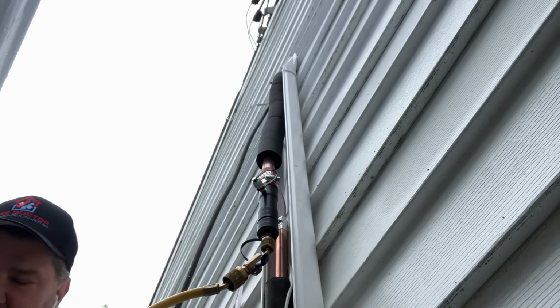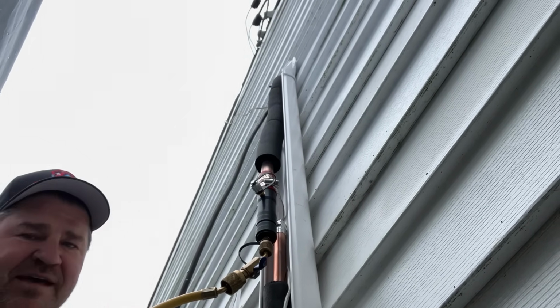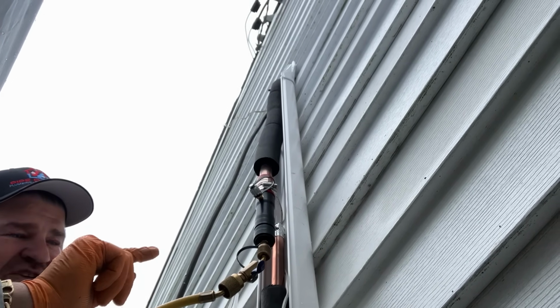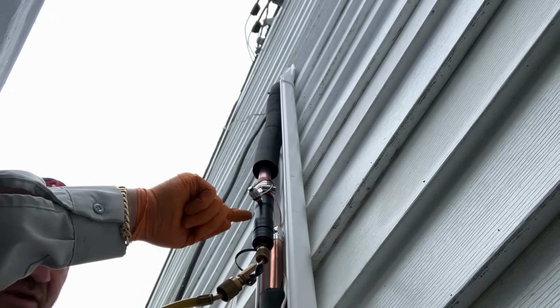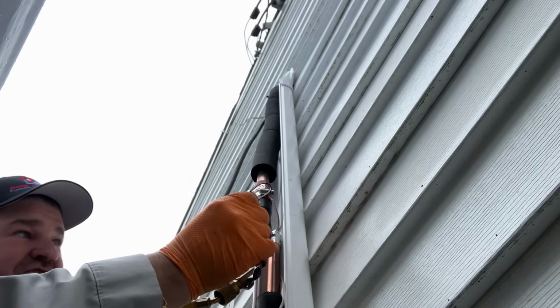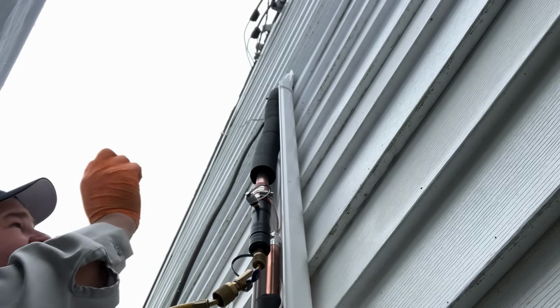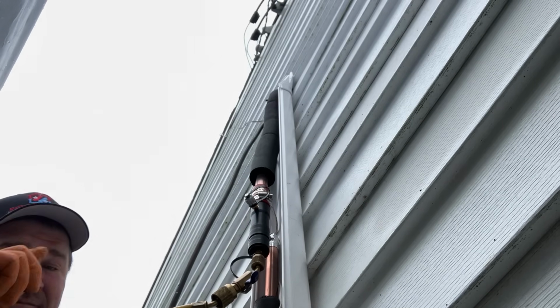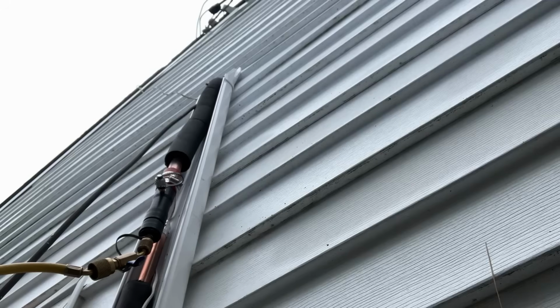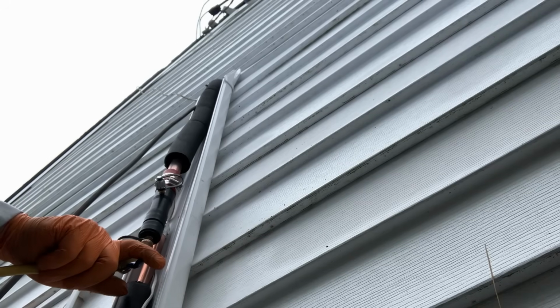All right, so I have my nitrogen tank hooked up, I'm at 400 PSI. As soon as Daniel gives me a call, I'm going to open up this valve, and that piglet right here is going to shoot into this 7/8 line and run about 100 feet to the other side of the house. Hi, you're good, you ready? All right, here comes the first one.